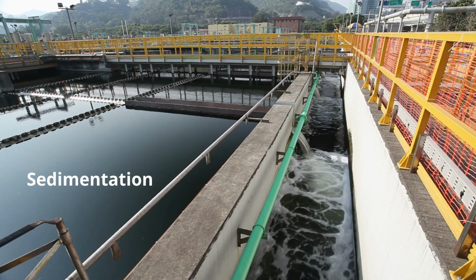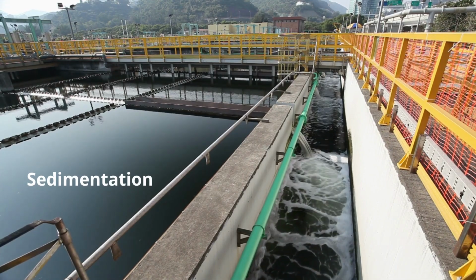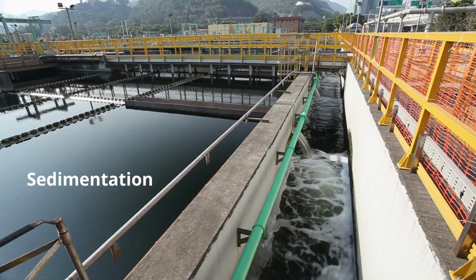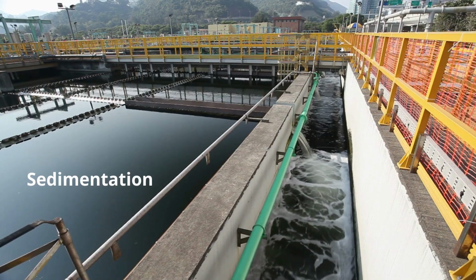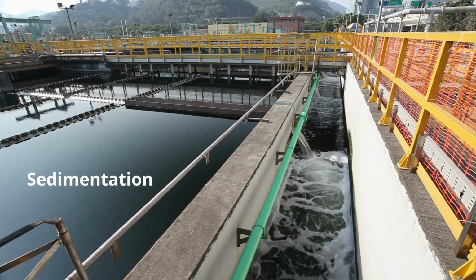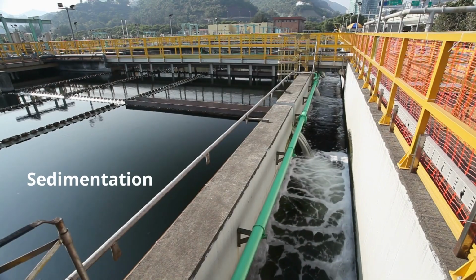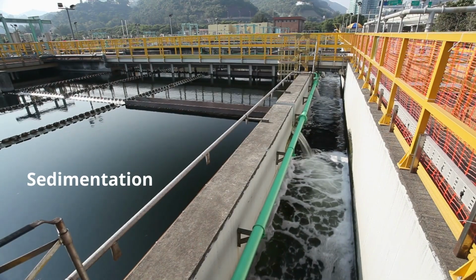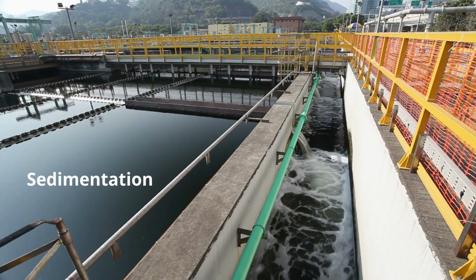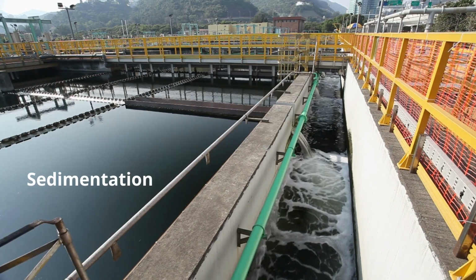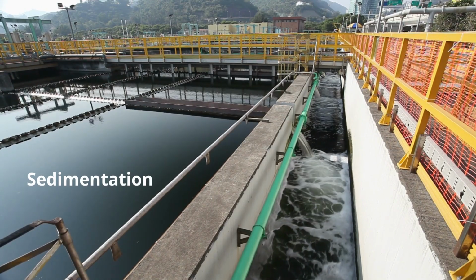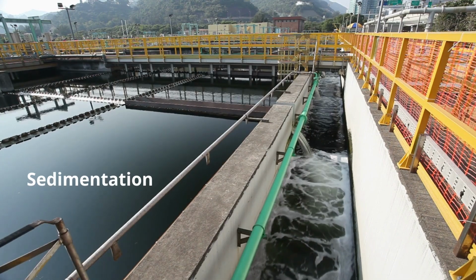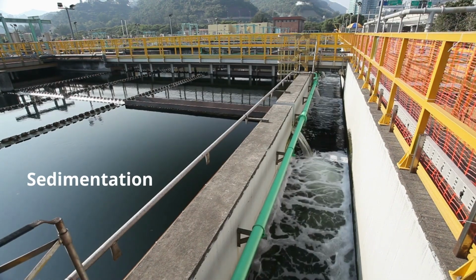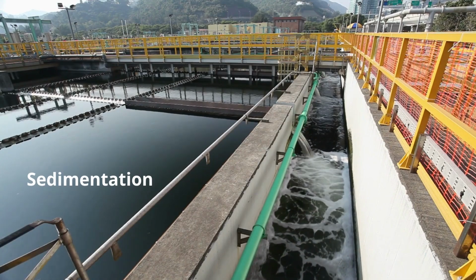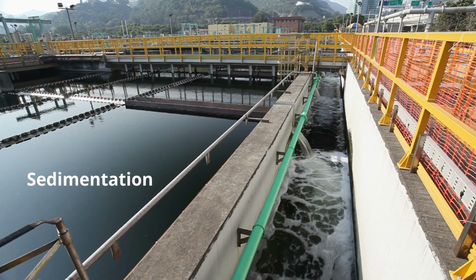As the water makes its way toward the weir, the large floc particles are allowed to settle out to the bottom of the clarifier. A rake continuously travels across the bottom of the clarifier and scrapes the settled floc to the center of the unit. Pumps are used to pull the settled sludge out of the clarifier and send it to a disposal pond. The water that passes over the weir is collected and transferred to the filters.